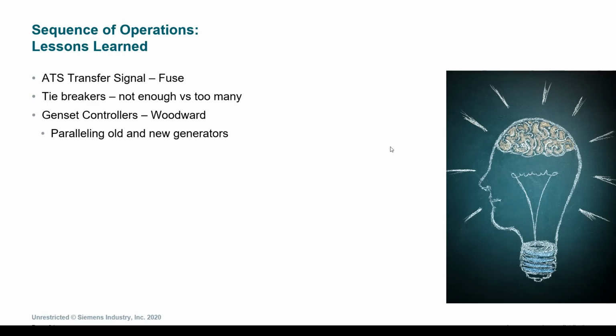Next, we want to make sure that any time generators are controlled new with older generators, that the actual genset controllers are identified as part of the project scope. This would include possibly upgrading to the new Woodward controllers to allow that functionality and specifically the communication between the generators for the paralleling.